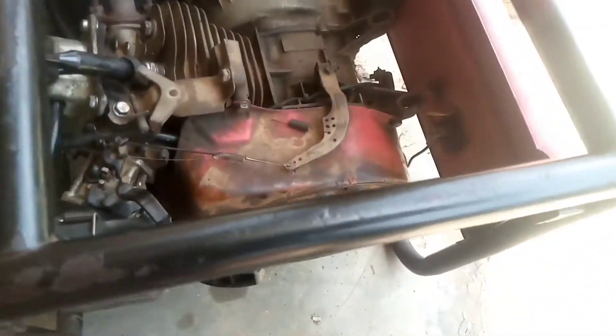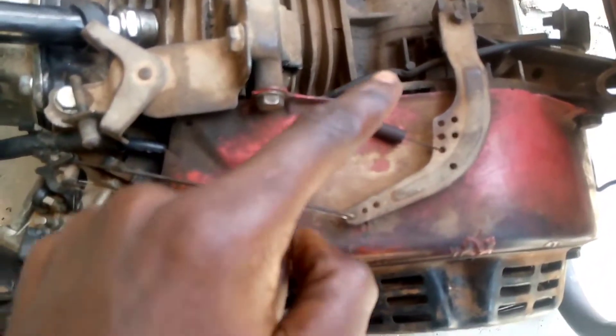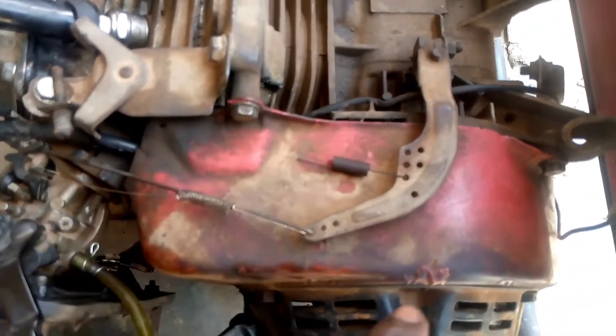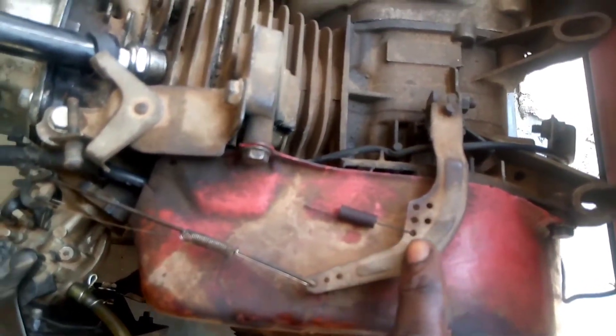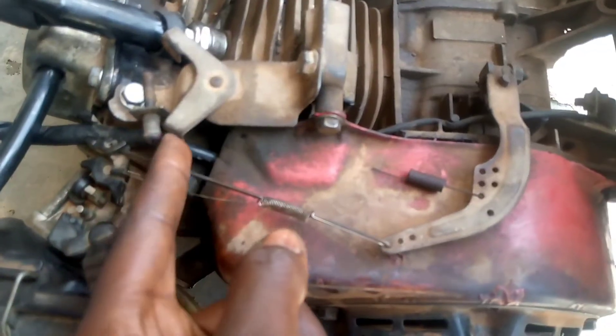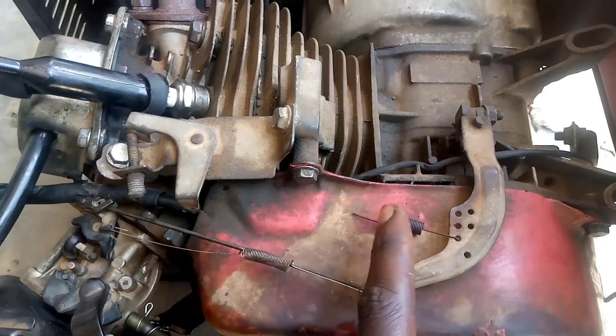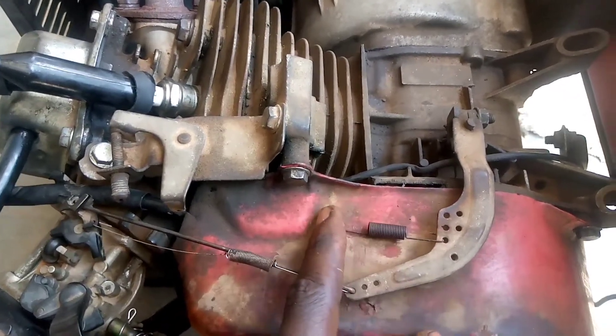As you can see, we've loosened the tank. The spring has caught the governor's spring. As you can see, the spring is the cause of the low current and the low voltage. It's attached to this place — you can see it's rusted already. So we're going to replace this governor's spring.